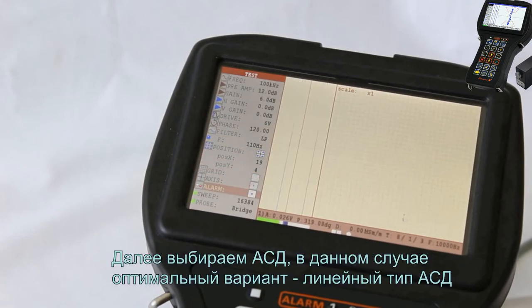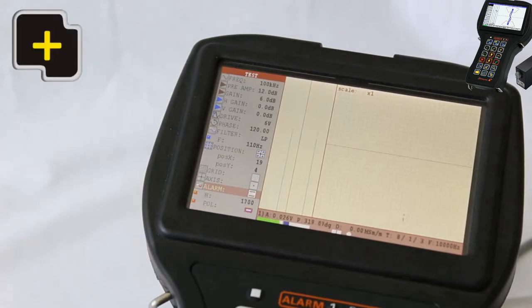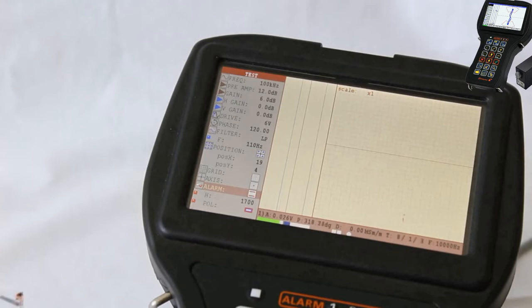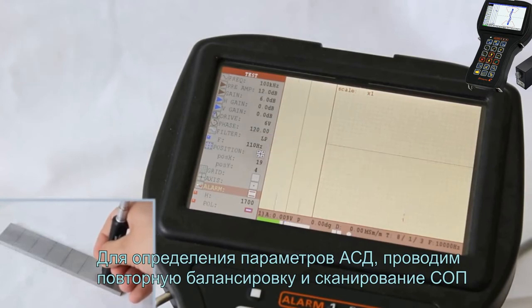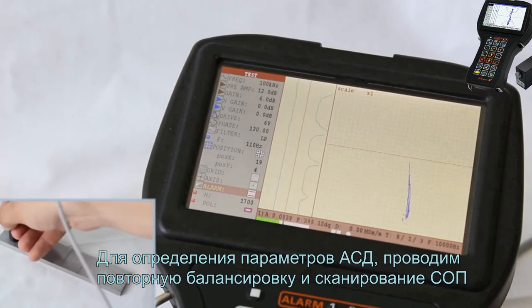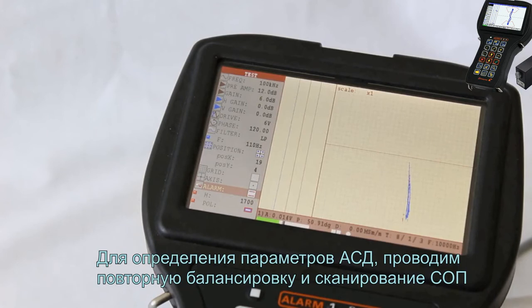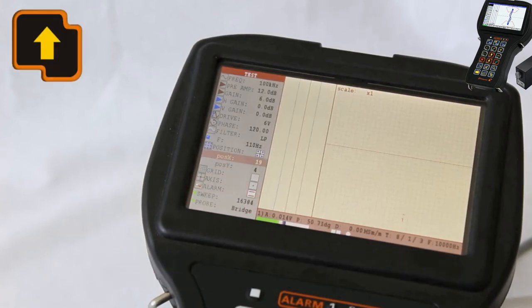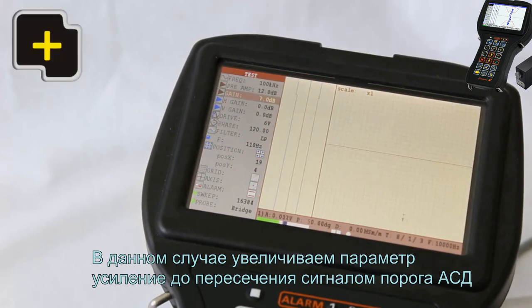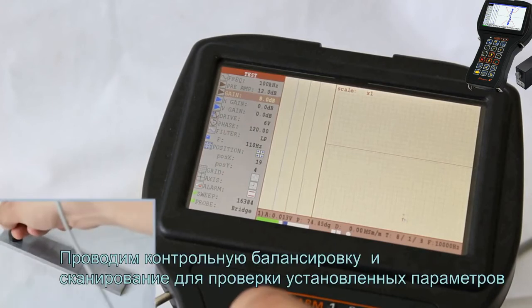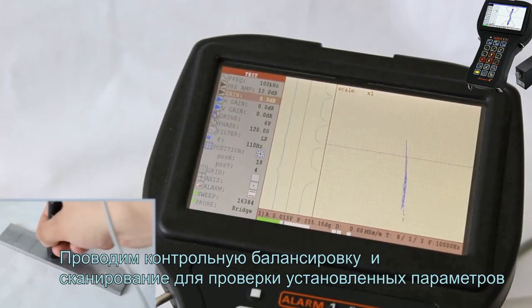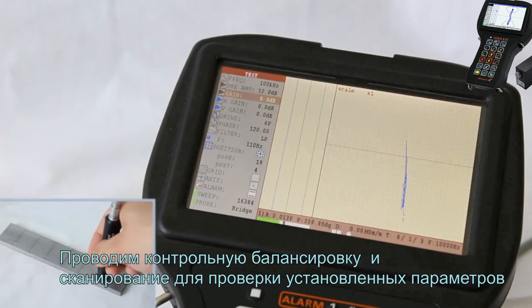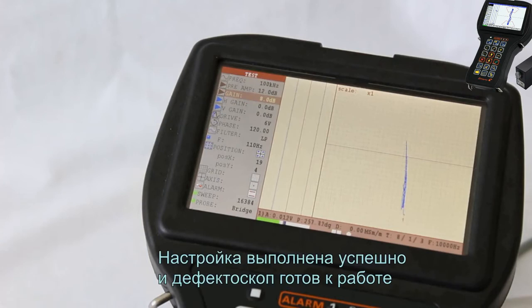Then select the alarm. In this case, the most suitable variant is the linear type of alarm. To determine the alarm parameters, perform the confirming, balancing and scanning of calibration block. In this case, we are increasing the gain parameter until the signal crosses the alarm threshold. Perform the confirming, balancing and scanning to check the setup parameters. The setup was successful and the flaw detector is ready for operation.